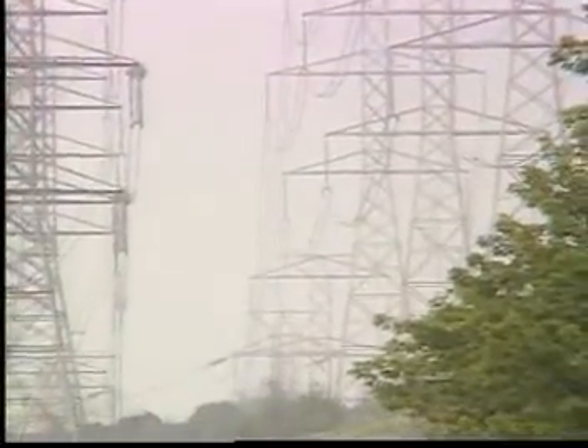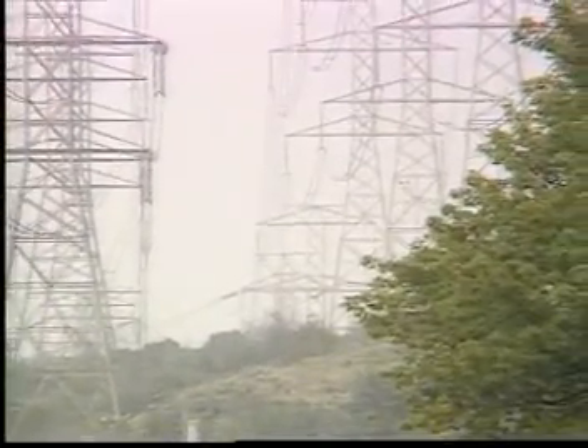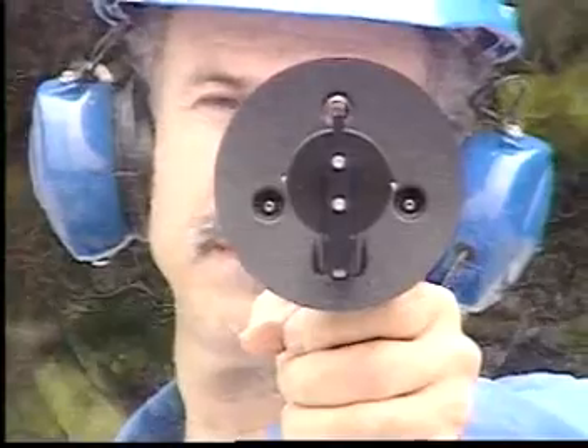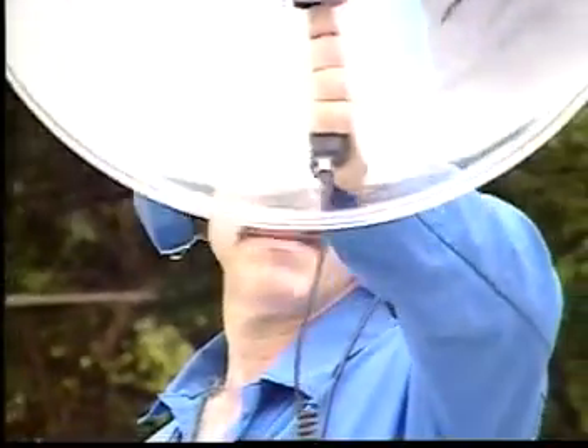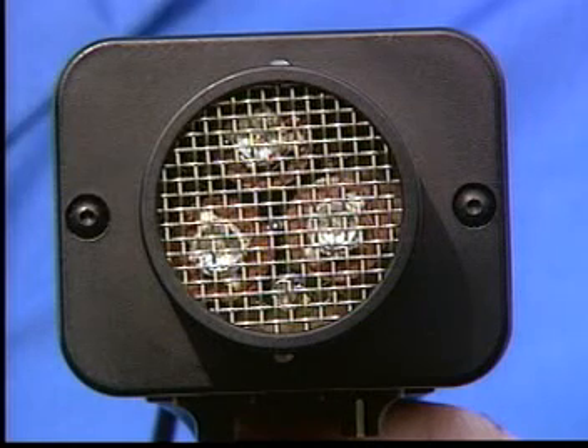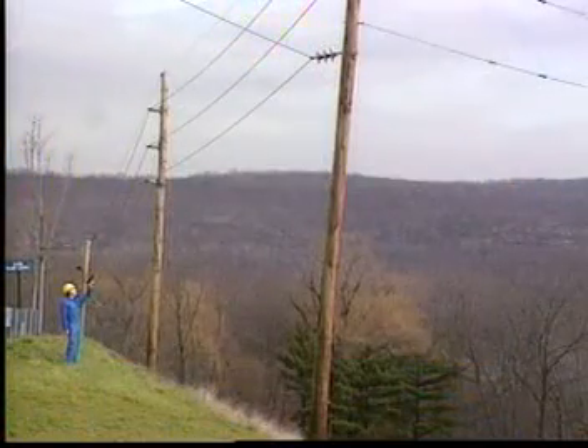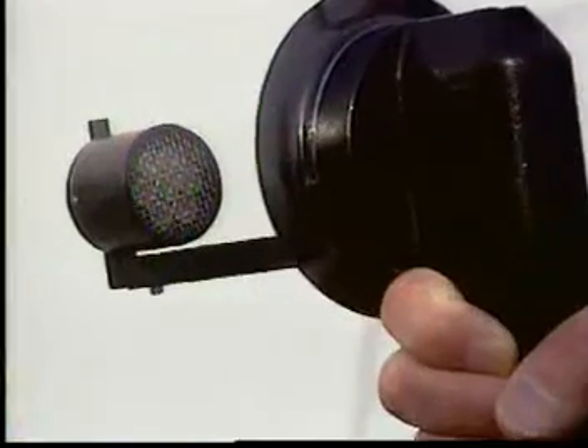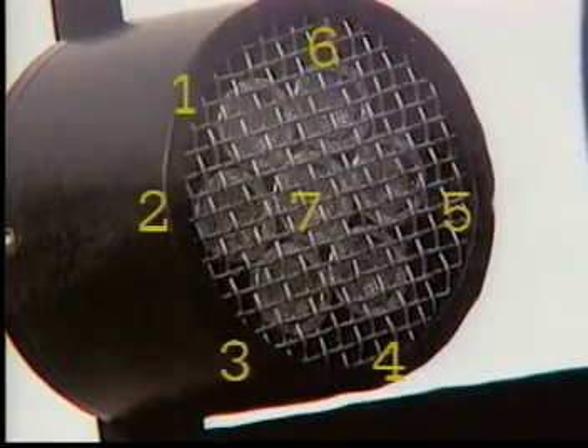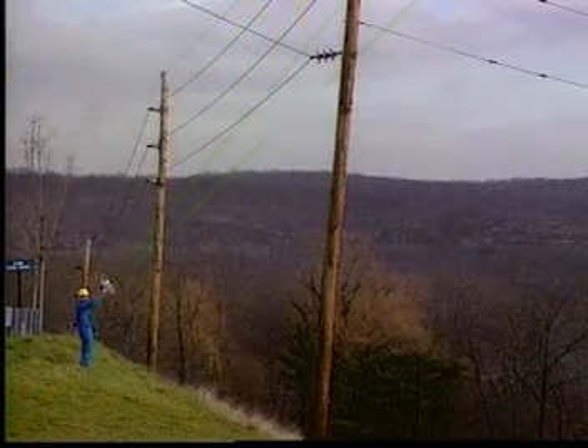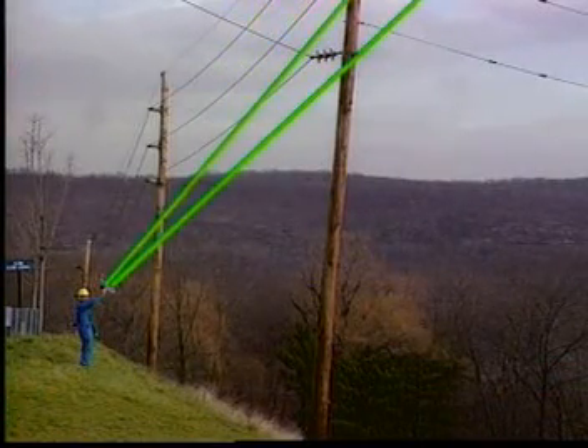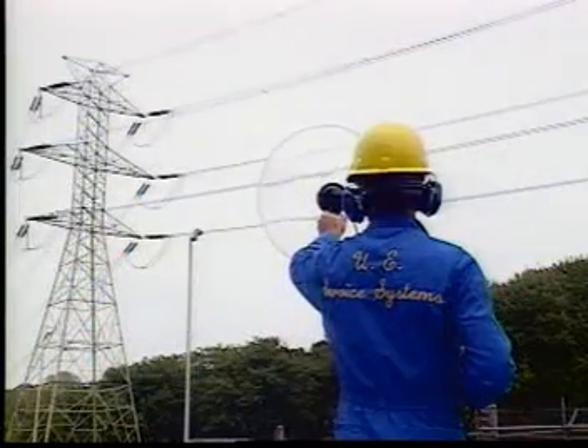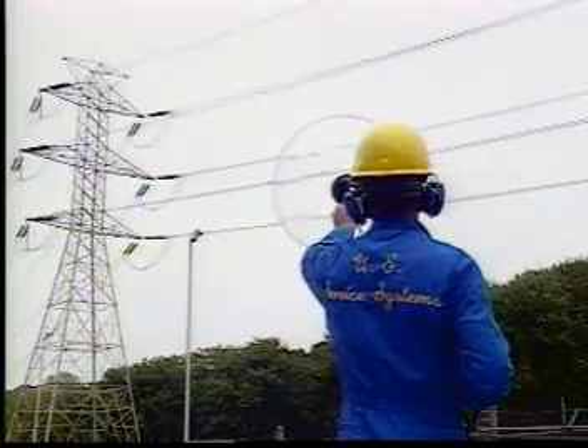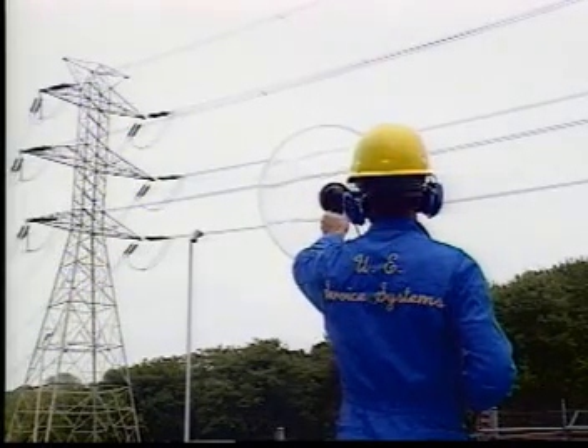For some situations, more advanced ultraprobe techniques are required. For testing high-voltage equipment at a safe distance, for example, the parabolic reflector is used. The standard ultraprobe scanner, the patented trisonic scanning module, has 3 transducers, and its field of detection tends to widen with distance. The parabolic reflector has 7 transducers, making it a powerful add-on for special purpose and long-range testing. It has a very tight, narrow band of detection, making it extremely directional. Its special shape and sighting mechanism enables users to locate an exact trouble spot at distances exceeding 200 yards.